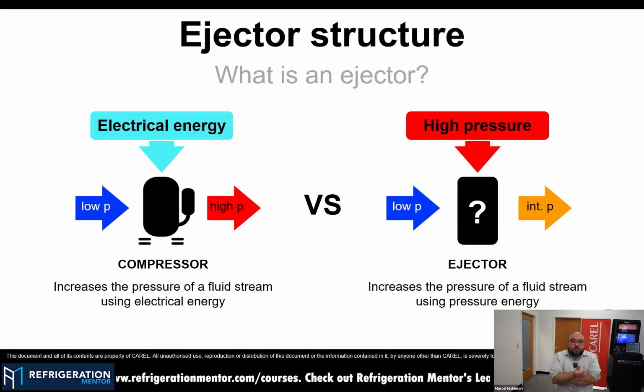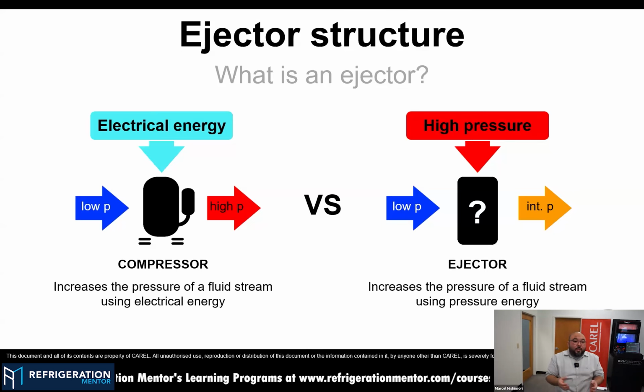So we can be energy saving when the system is performing at high pressure. A lot of people ask me, what technology is better? Is it better to have an ejector? Is it better to have a subcritical system? What if? So normally my answer for this type of question is that when you have a system that needs to operate at high ambient temperatures, like Phoenix, Arizona, where you have very high temperature for a certain period of the year, every system down there will have a higher energy consumption. So what we can do is improve this energy consumption, adding some other technologies that can make more efficiency for the same energy power that you are consuming. If you compare a transcritical system with ejector to a subcritical system, subcritical would always be better, but not always can you get that, like in warm regions, Florida, even Phoenix, Arizona. So in all these regions where during summer you have high ambient temperatures, you cannot operate with subcritical. So the ejector comes and makes a better effect in that type of region.